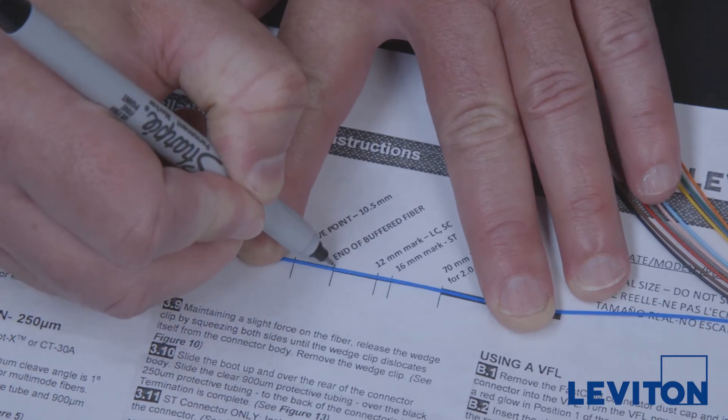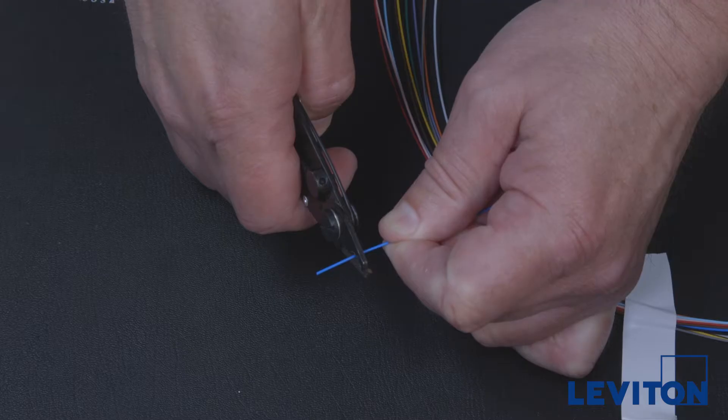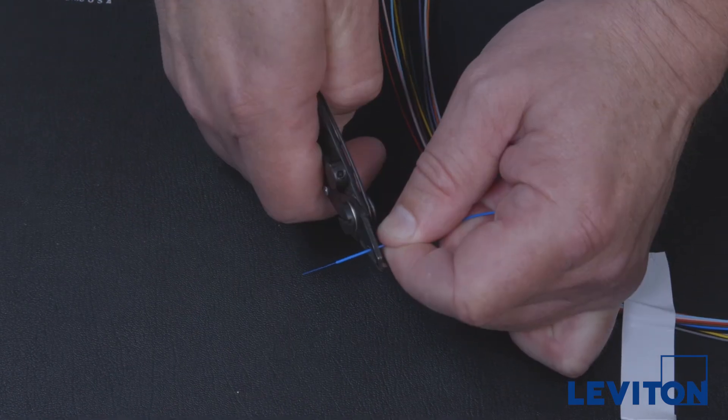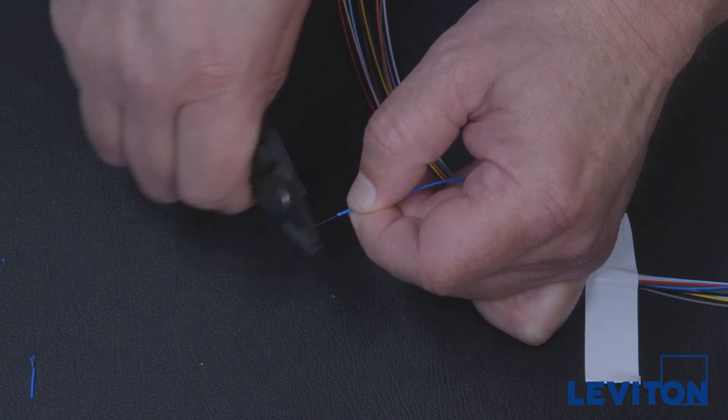Make a mark on the tubing 12 millimeters back from the exit point of the fiber. Run the fiber stripper over the bare fiber, ensuring complete removal of the acrylate coating. Verify the acrylate coating has been removed from the fiber.